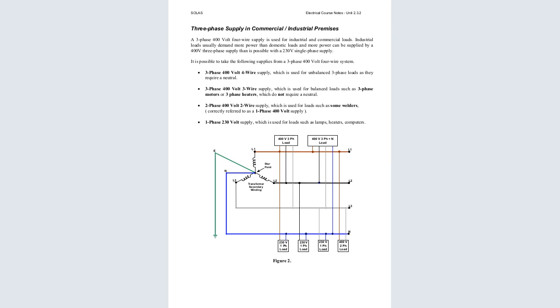The industrial loads usually demand more power than the domestic loads, and more power can be supplied by a 400 volt three-phase supply than is possible with the 230 volts single-phase supply. So it is possible to take the following supplies from a three-phase 400 volts 4-wire system. A three-phase 400 volts 4-wire supply is used for unbalanced three-phase loads as required. They require a neutral.